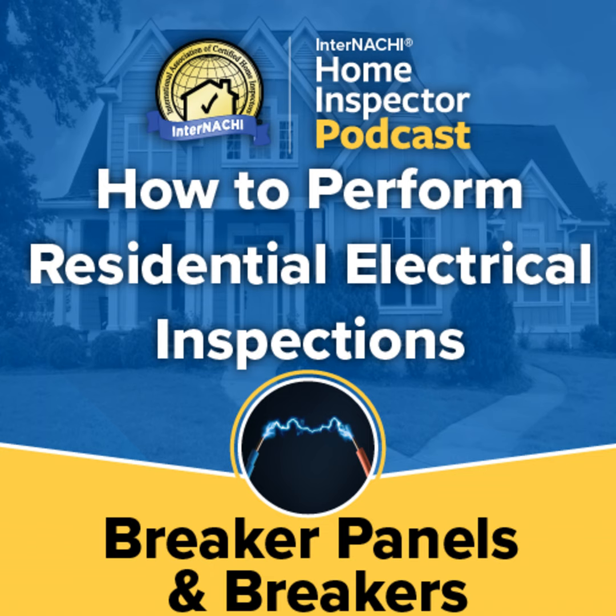240-volt circuit breakers. Our homes require high voltage and amperage circuits to run appliances such as dryers, air conditioning, stoves, and additional breaker panels. Appliances that are 240-volt are fed from 2 120-volt conductors, each connected to a separate bus bar in the electrical panel board. It is imperative that when one of the circuits trips due to an overcurrent condition, both conductors are de-energized at the same time. If not, someone could be trying to repair an appliance that is still partially live.